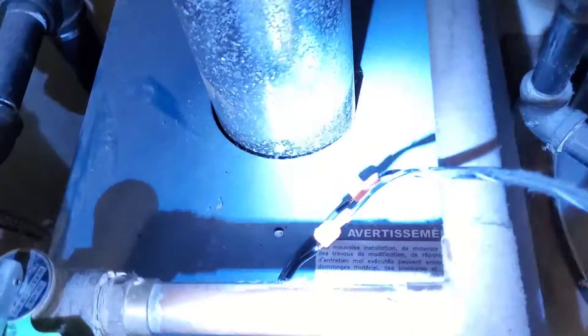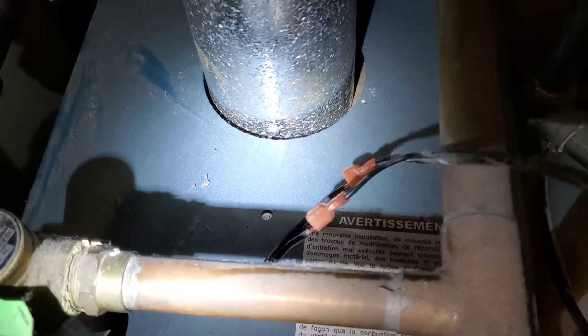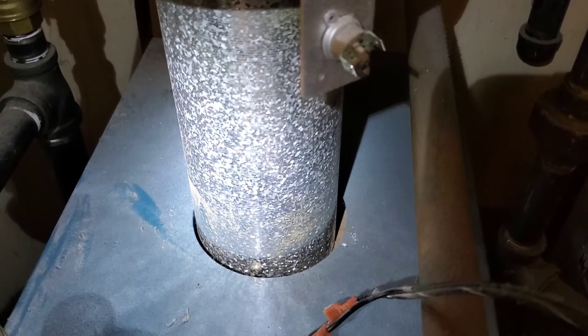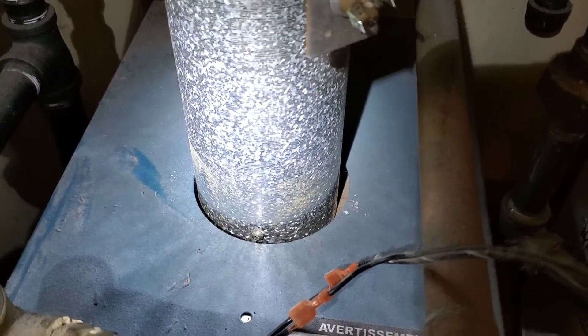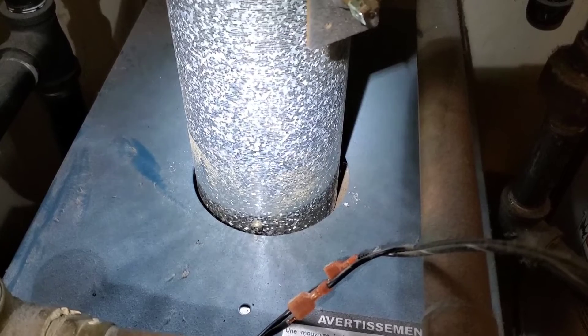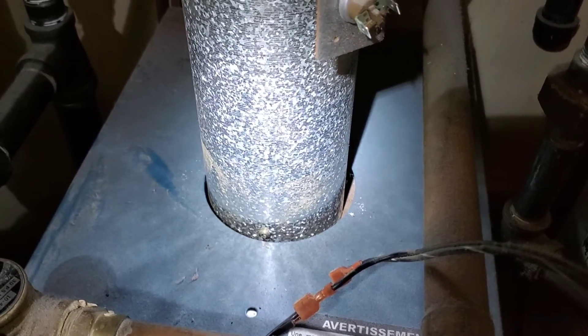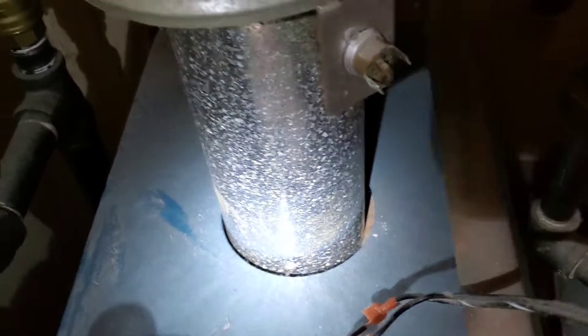Here I'm using a jumper to test this blocked vent switch on this hot water boiler. By putting a wire where the vent switch would be, I'm completing the circuit — taking the vent switch out of the circuit to see if that is what the problem is. This is a very simple, cost-effective way to test circuits if you have problems.